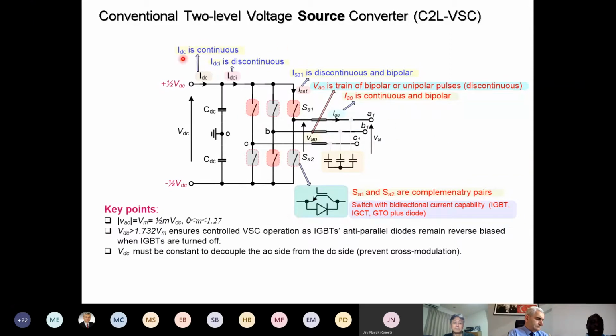And the key points from these basic topologies are, first of all, the peak of the fundamental AC voltage produced at this point is defined by these expressions, which is half times the modulation index times VDC, and the modulation index can vary from 0 to 1.27. And the VDC must remain above the peak of the line-to-line voltage to have control operation. This is necessary to prevent the AC voltage imposed by the grid from turning these diodes on uncontrolled.